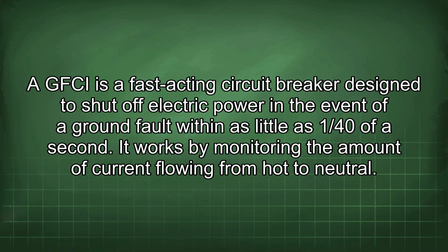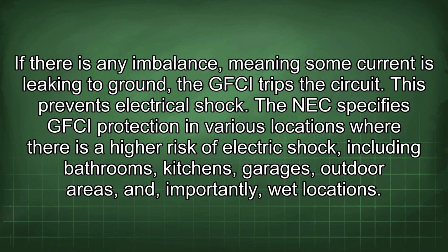It works by monitoring the amount of current flowing from hot to neutral. If there is any imbalance, meaning some current is leaking to ground, the GFCI trips the circuit. This prevents electrical shock. The NEC specifies GFCI protection in various locations where there is a higher risk of electric shock, including bathrooms, kitchens, garages, outdoor areas, and, importantly, wet locations.